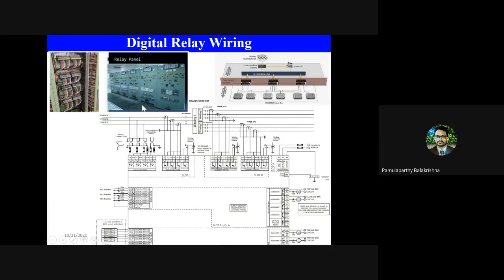So you can see these are the relay panels. This is how relays are installed in a control room. You can see these are the relays. At the back side of the relays you can see the wires, which are nothing but the various signals that I was mentioning, coming from the field. For example, if this is a transformer protection relay, all the various signals of the transformer come to this panel, and in turn go to the relay for operation.